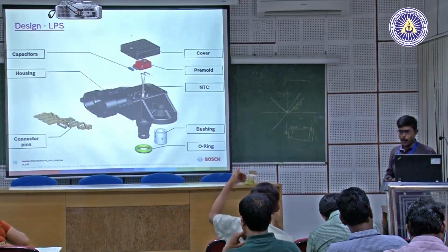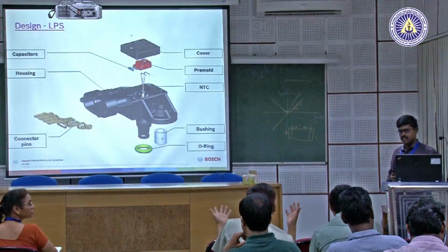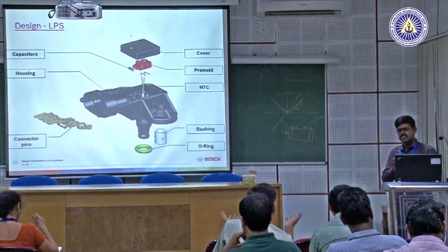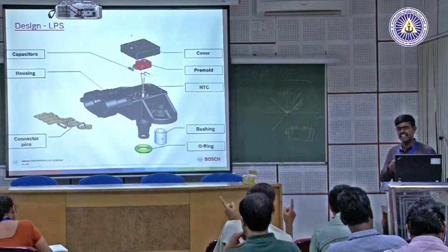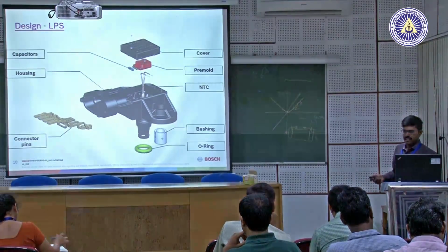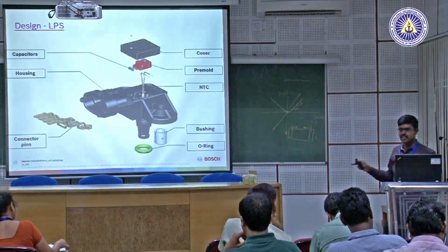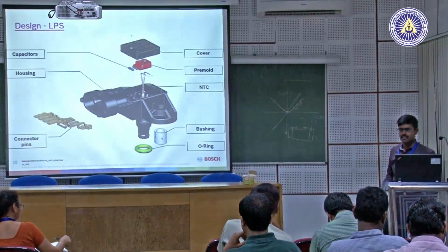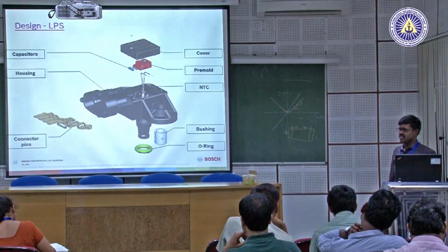I want to know how you are maintaining the vacuum level in that chamber, because leakage will be there. That's a completely closed one. In the process, it is taken care of. Yeah, it's completely sealed. But what is the leakage of those seals? Absolute, zero. That cannot be zero. So what is the leakage rate? It has practically some leakage.